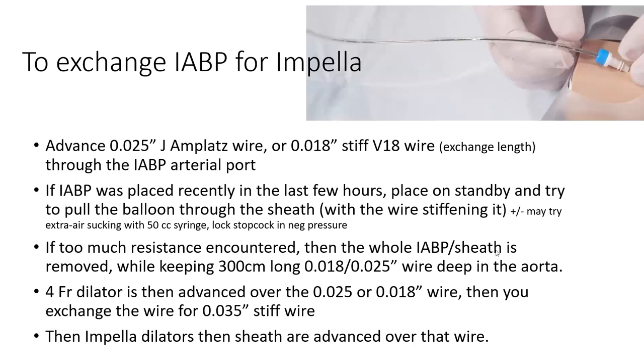Then the whole balloon pump sheath is removed. So you're keeping the wire deep in the aorta. It's a long 300 centimeter 0.025 or 0.018-inch wire. Keeping it deep in the aorta, then you're taking the whole balloon pump catheter and sheath out while somebody is pulling out while another person is ready to hold pressure. You pull them both while the wire is still in.